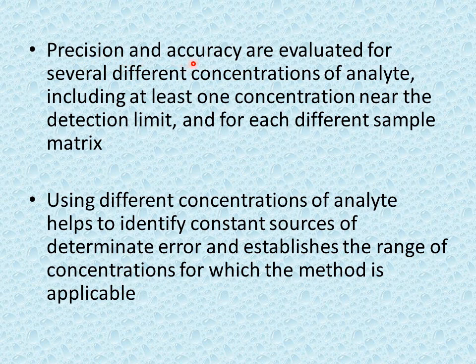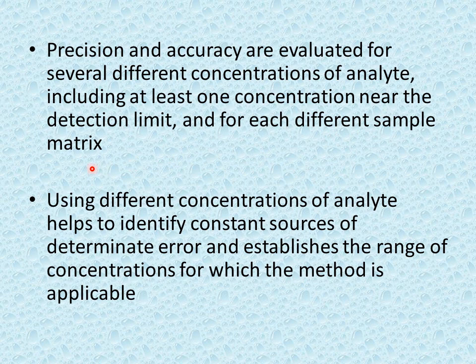Precision and accuracy are evaluated for several different concentrations of the analyte. These parameters are not measured using only a single concentration; rather, they are evaluated using a variety of concentrations, including at least one concentration near the detection limit. These are also evaluated for each different sample matrix, so for different samples with different concentrations and sample matrices, precision and accuracy are all calculated.